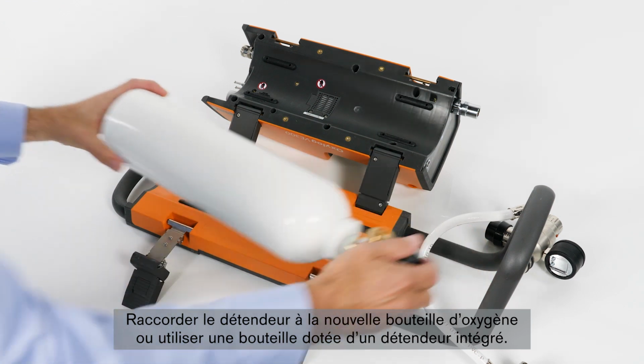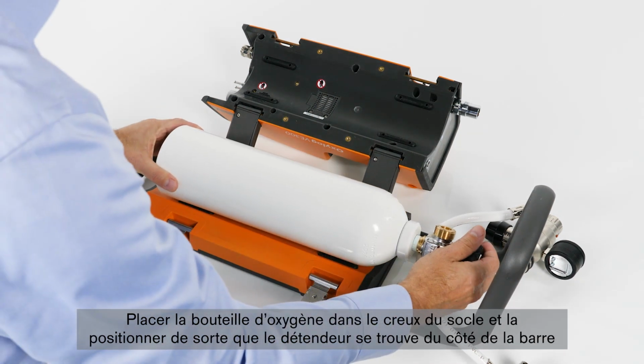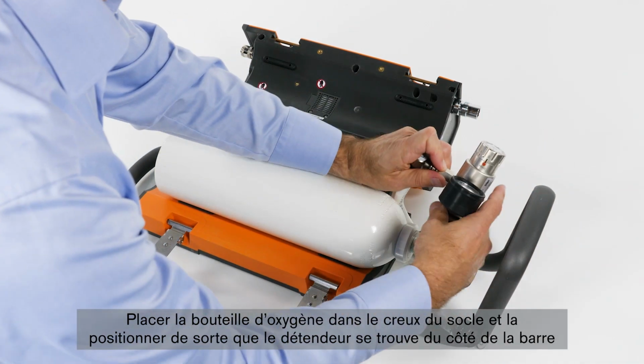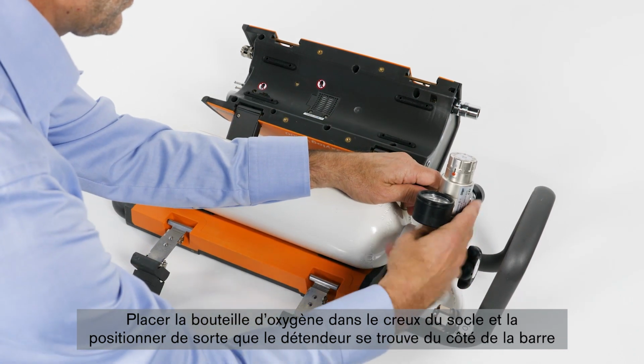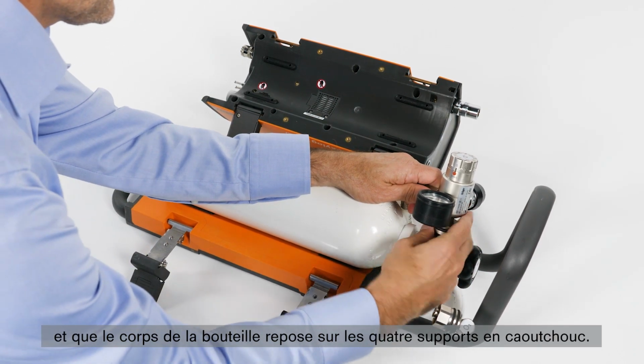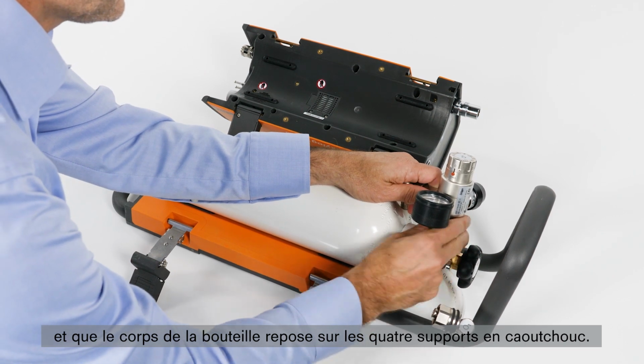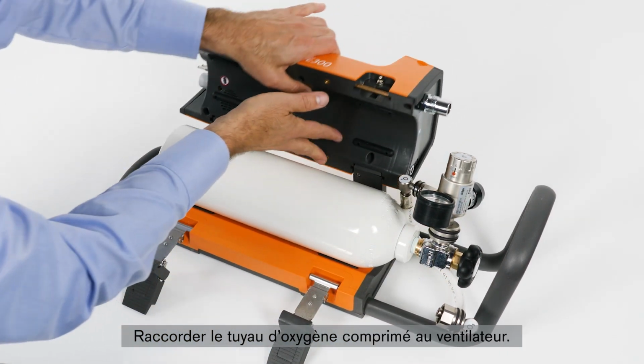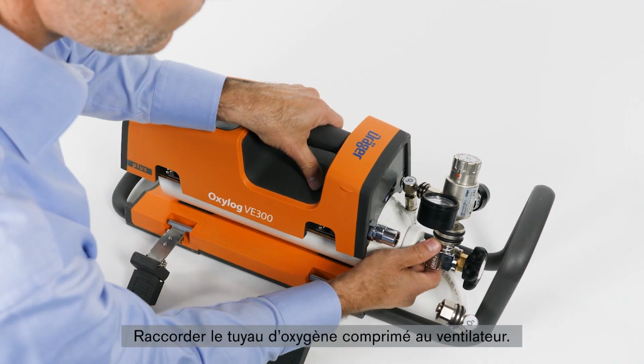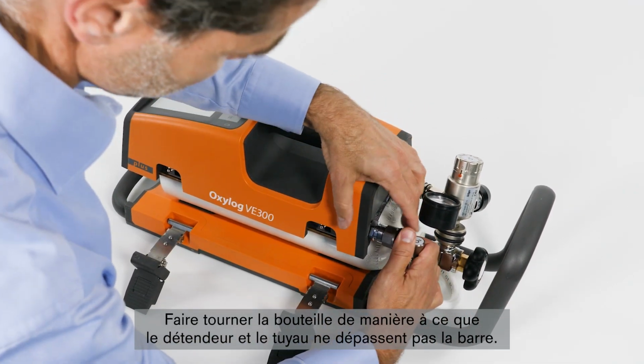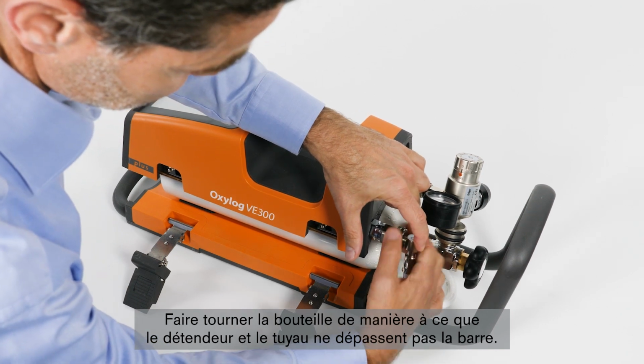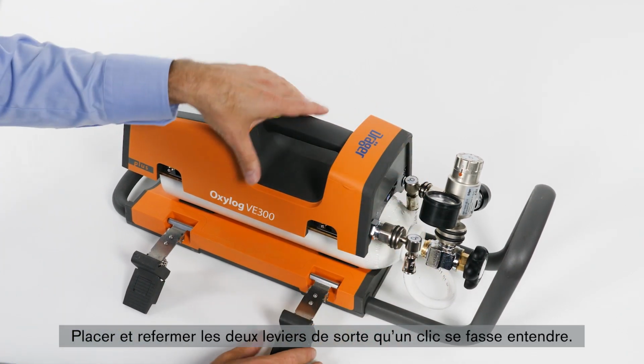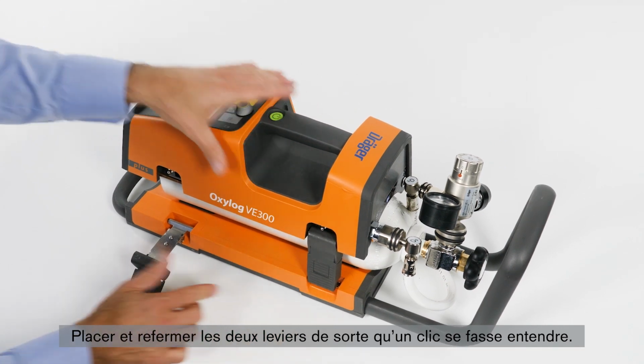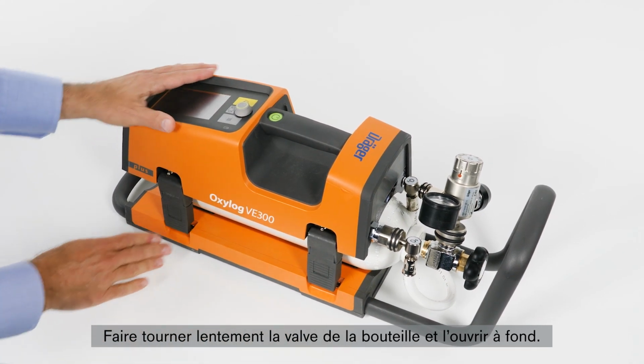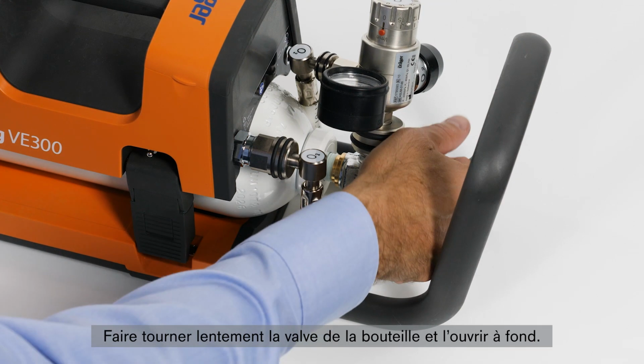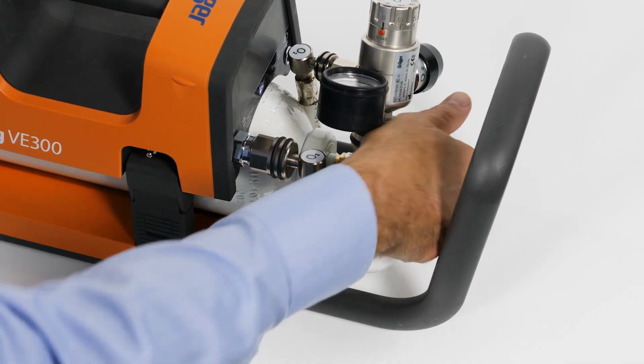Connect the pressure reducer to the new oxygen cylinder, or use an oxygen cylinder with an integrated pressure reducer. Place the cylinder in the well of the base plate and position the oxygen cylinder so that the pressure reducer is on the side of the bar and the cylinder body is resting on all four rubber feet. Connect the oxygen compressed gas hose to the ventilator. Rotate the cylinder so that the pressure reducer and the hose do not protrude beyond the bar. Attach and fasten both closures until they engage audibly. Rotate the cylinder valve slowly and open it fully.